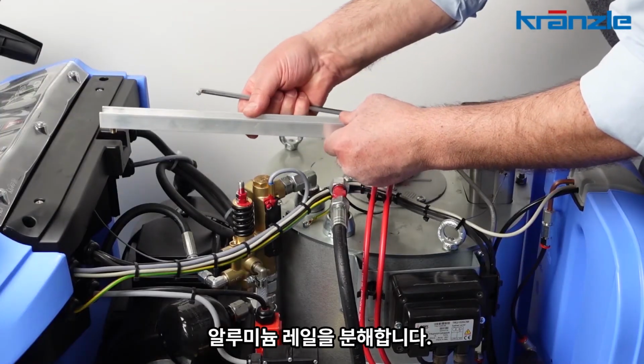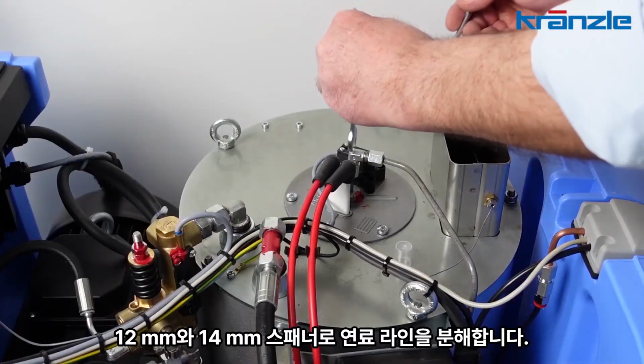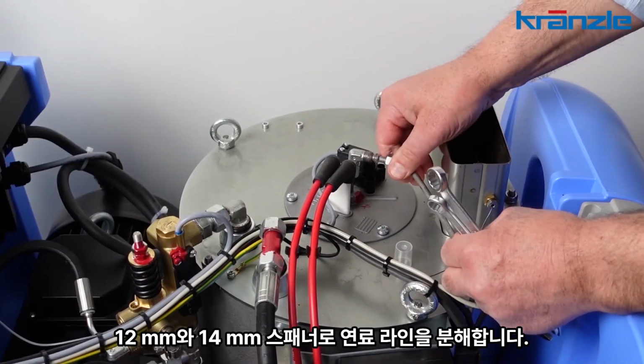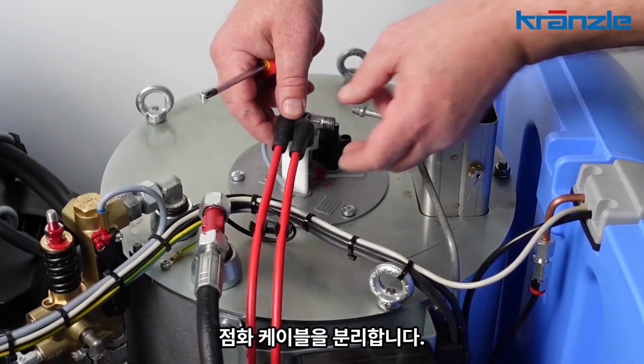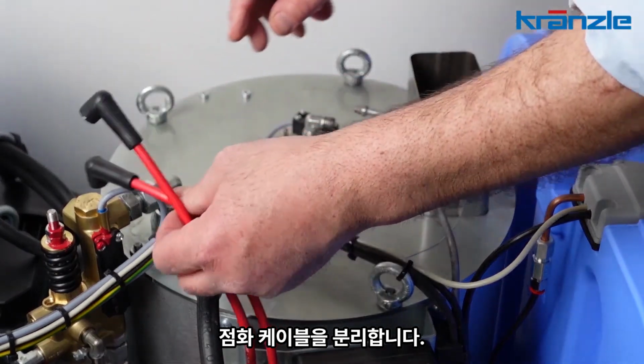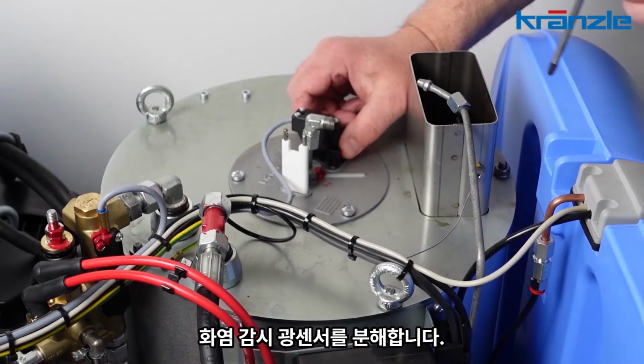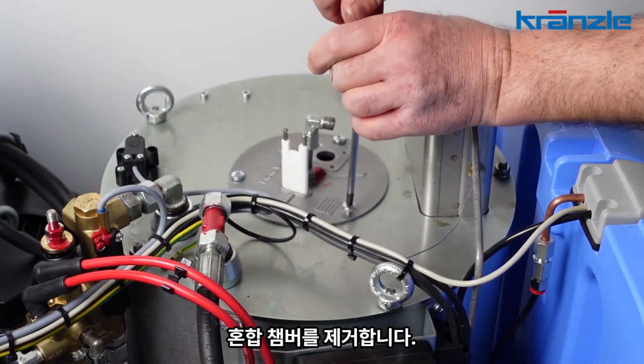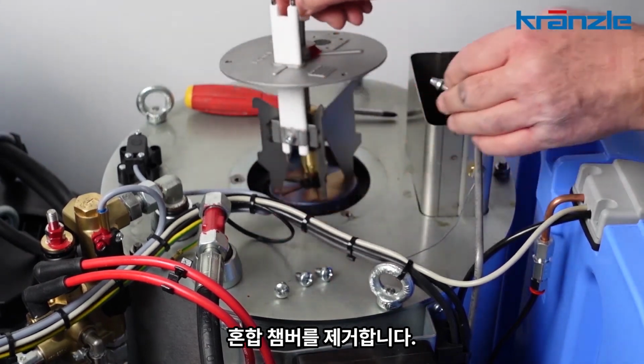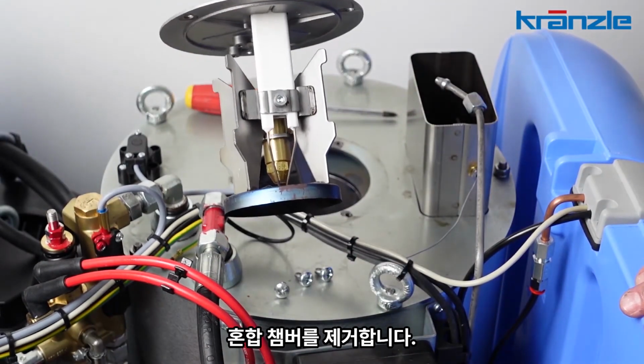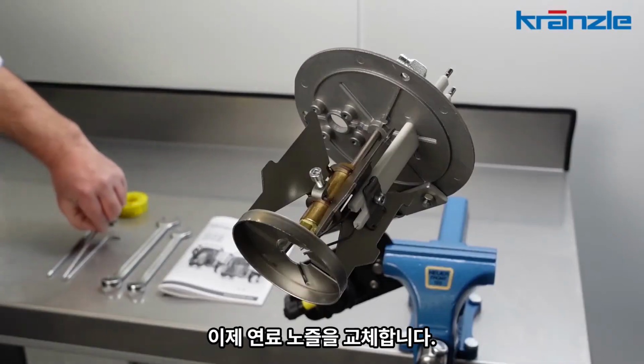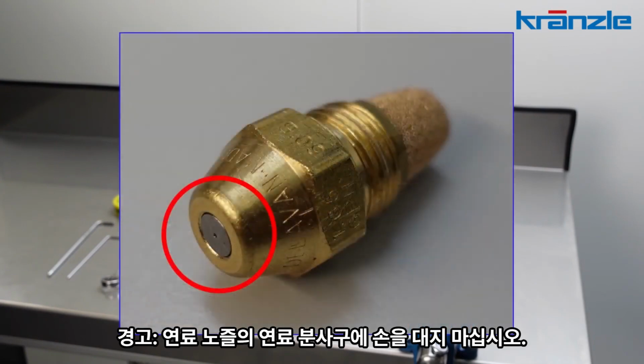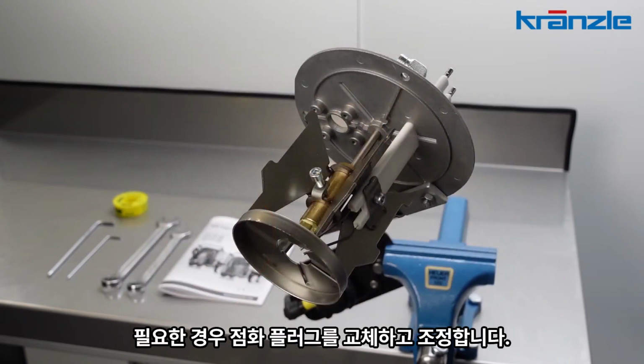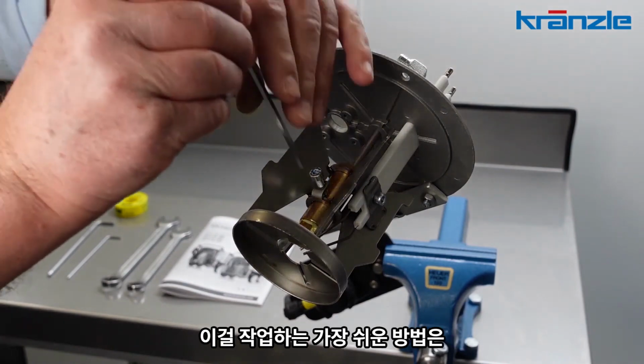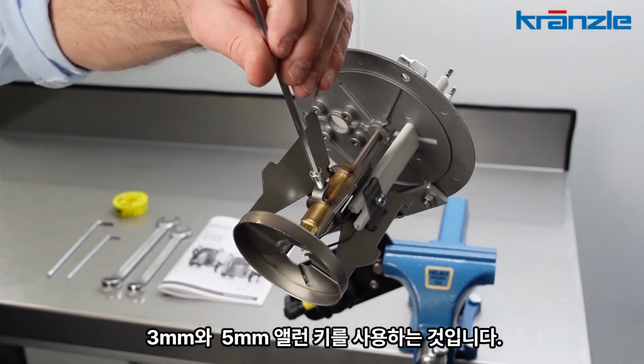Dismantle the aluminium rails. Dismantle the fuel line with the 12 and 14 wrench. Disconnect the ignition cable. Dismantle the flame monitoring photocell. Remove the mixing chamber. Now we replace the fuel nozzle. Caution! Please do not touch the fuel outlet of the fuel nozzle. If necessary, also replace and adjust the electrodes. The easiest way to do this is with a 3 and 5 mm Allen key.